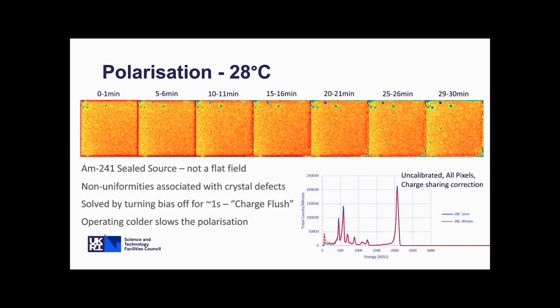You can operate the detector a little colder, and that slows down the amount of leakage current generated, which slows down the polarization effect. So there is some customization that we can do around this to optimize it for different applications as well. Again, that's something to speak to Quantum Detectors about if you have any particular needs about what collection times you need and continuous operation.